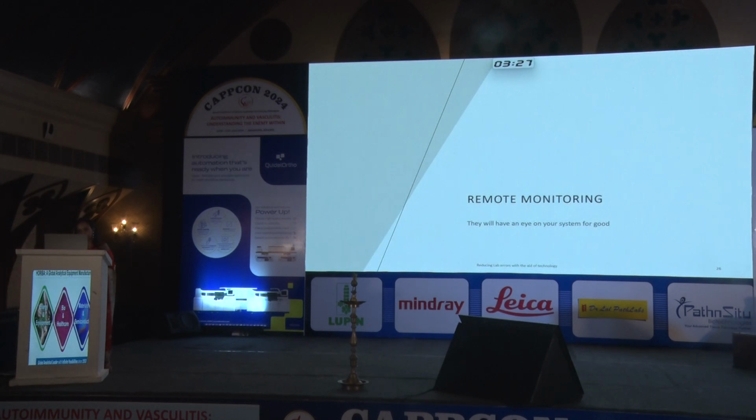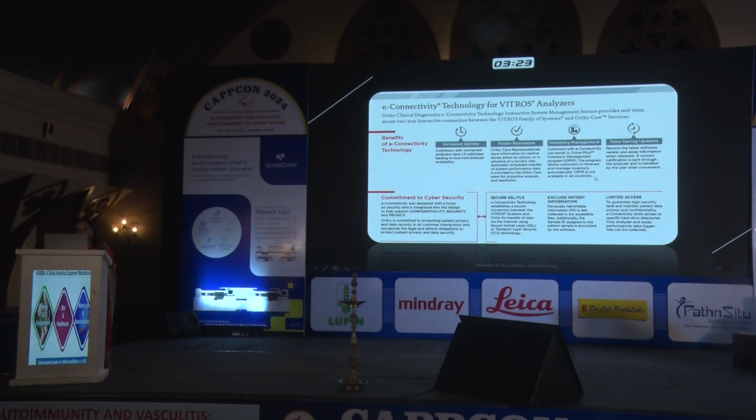And the final one is remote monitoring, which is again an advantage. There is a technology called e-connectivity technology, which is present in Vitros analyzers. It increases uptime, leads to faster resolution of any breakdown call, allows inventory management, and also there are time-saving updates, and all these features with a commitment to cybersecurity. Hence, e-connectivity through remote access is a great way of increasing machine uptime and decreasing downtime.